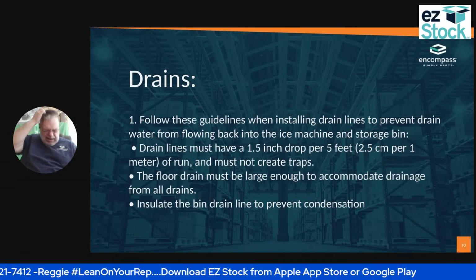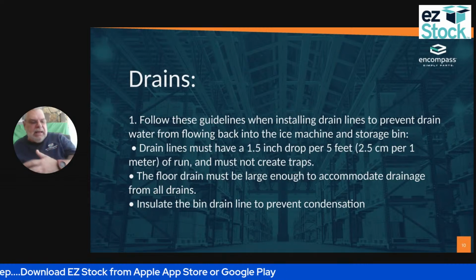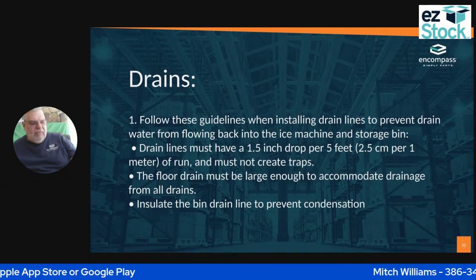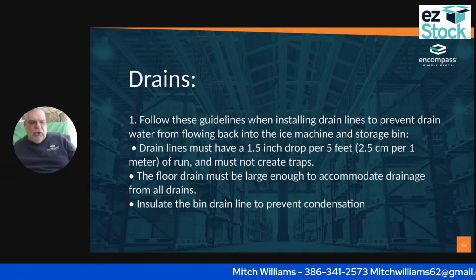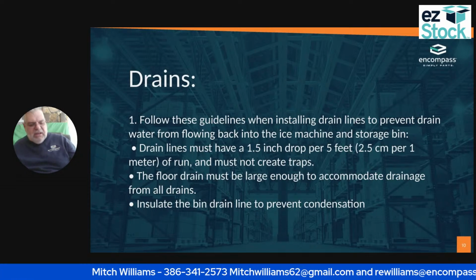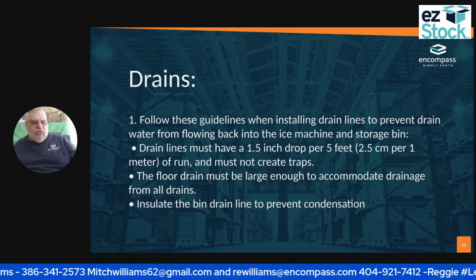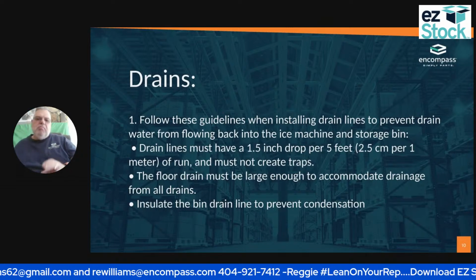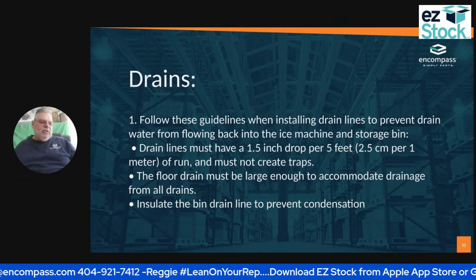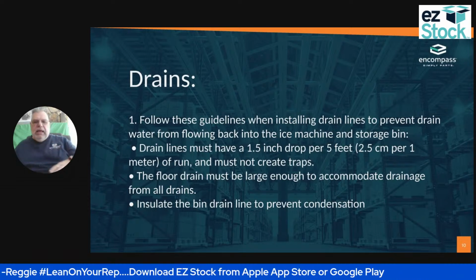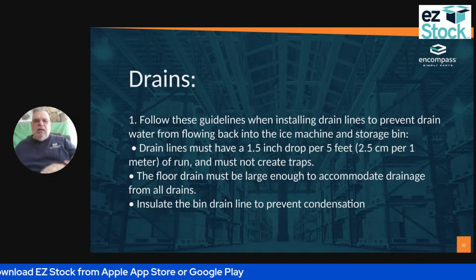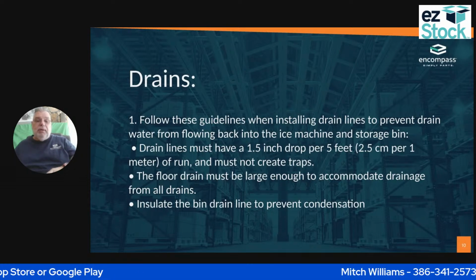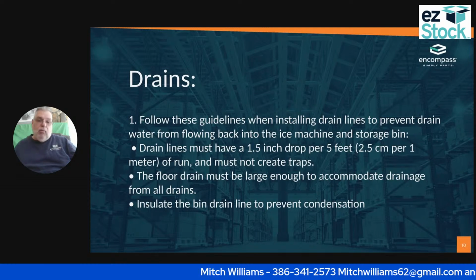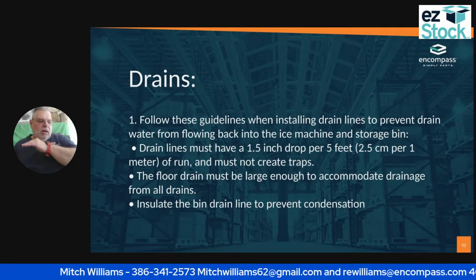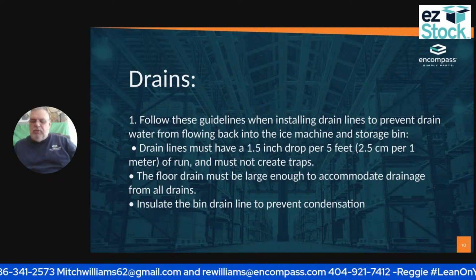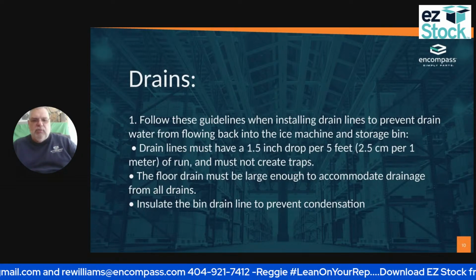So what does that mean? Simply that if I have a foot of line, say 5 feet of line for a drain, it's got to drop at least 1 inch. If I don't have that, I may have to put a pump on it. Every unit we had that was inside a building, we always put a pump on it. We may use that drain pump to push the water out and make sure we have no leakage. That's one of the things we made sure we had.